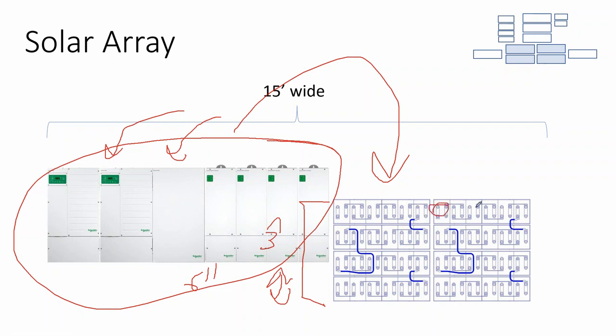Similarly, these battery cells need to be serviced. And what happens is every couple of weeks, you have to water the batteries. And watering the batteries is really easy. You take a watering container and you plug it into the side, and all of the cells have a watering system that interconnects them. It's almost like you take a super soaker and you squeeze the trigger and you just fill the batteries up with water, and they all fill up and stop when they're full.